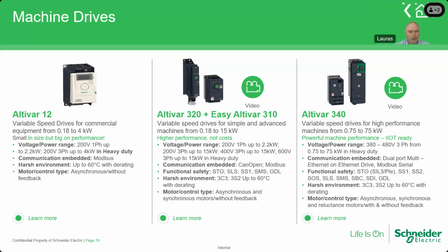So don't be surprised. The first product is Altivar 12, a simple drive, one power, one phase. So supply one phase 220 volts, output 3 phases 220 volts. It's used for different applications with small power motors, usually up to 2.2 kilowatts. We do not sell 3 phase 220 volt because we don't have that network, so we use only one phase in our market drive.